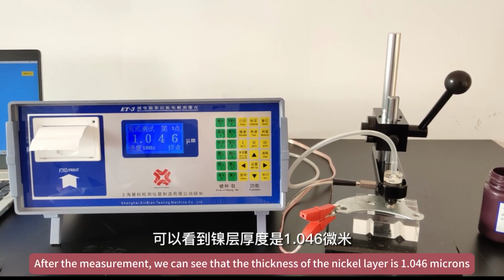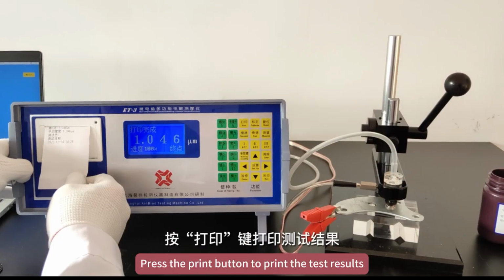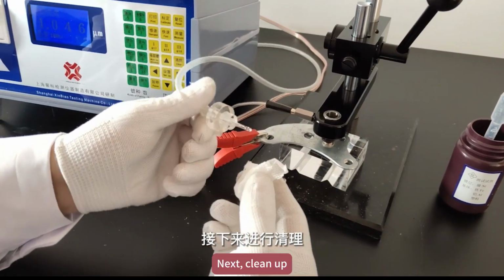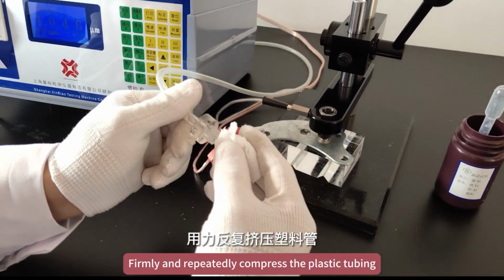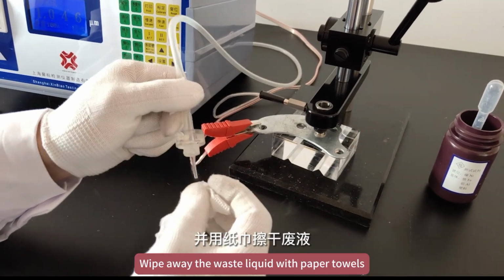After the measurement, we can see that the thickness of the nickel layer is 1.046 microns. Press the print button to print the test results. Next, clean up. Lift the stirring head. Firmly and repeatedly compress the plastic tubing. Empty the tube by squeezing out the liquid. Wipe away the waste liquid with paper towels.